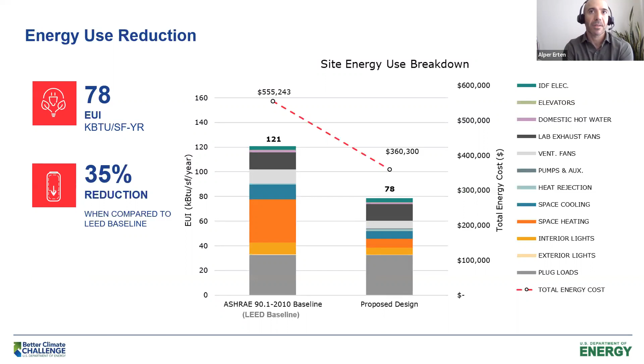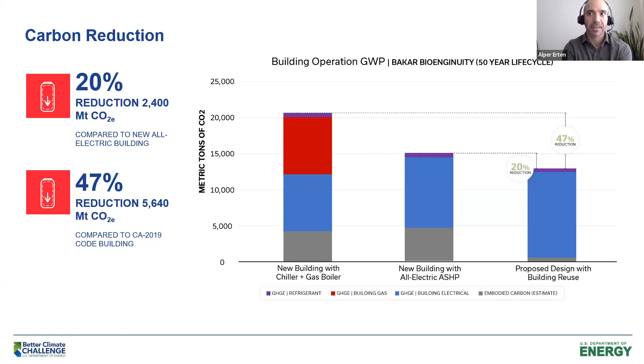And next slide. In terms of carbon, suppose we had built this building as a new building with a typical water-cooled chiller and a gas boiler central plant, and compare that to reusing an existing building and going all electric. The overall carbon emissions reduction, including a rough placeholder for embodied carbon over the 50-year building life cycle, was 47%. Around 27 to 30% of that reduction comes from the energy, the building emissions, with 20% coming from the reuse of the existing building. And next slide.